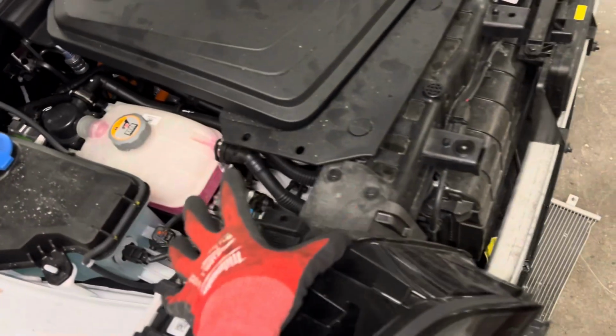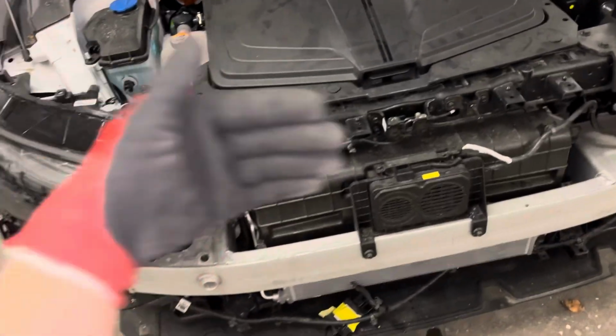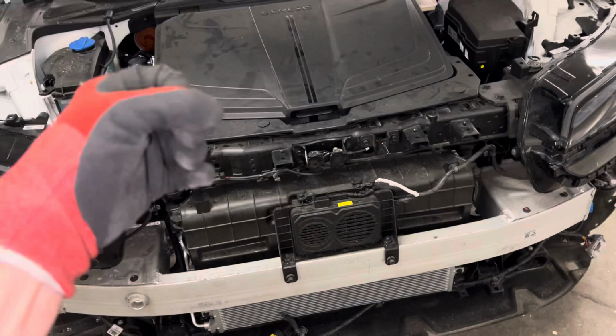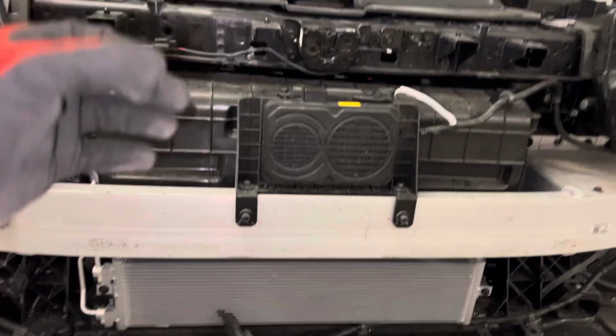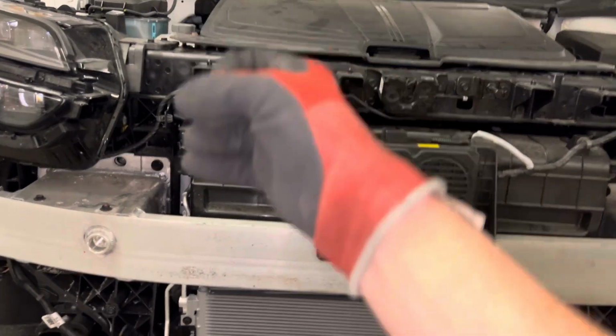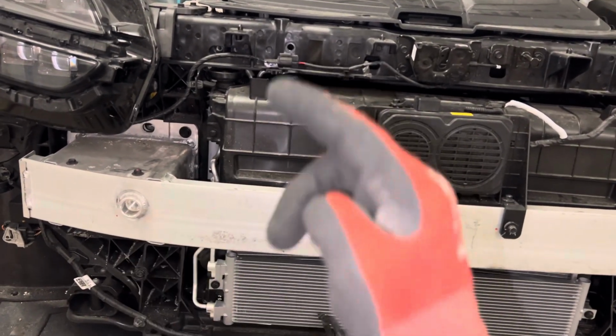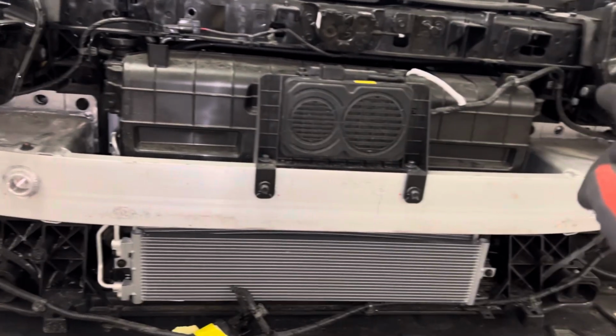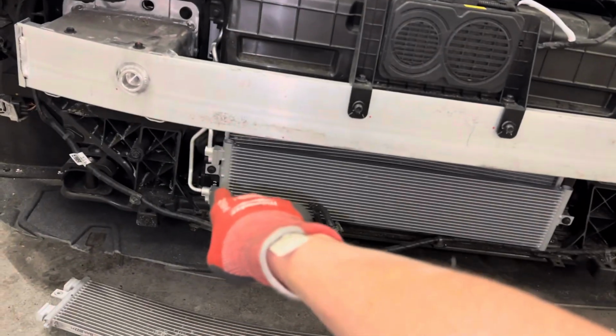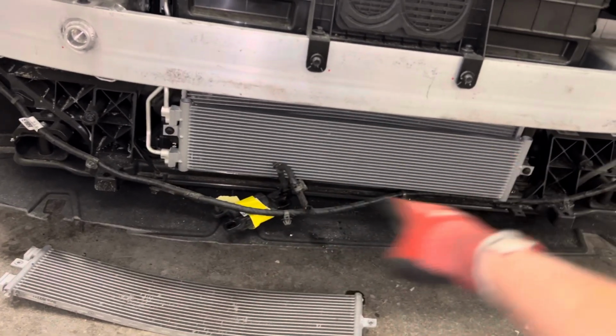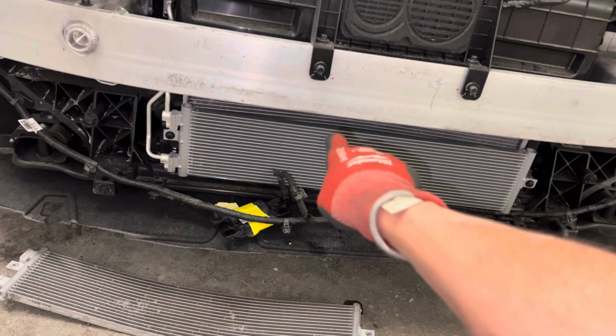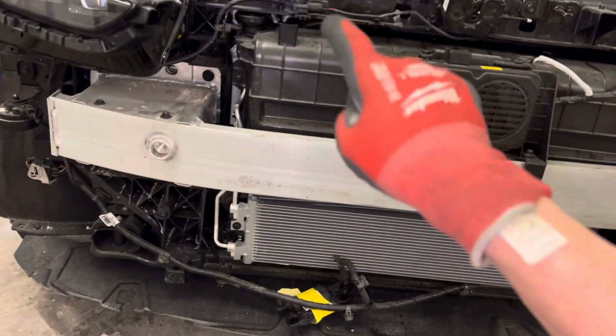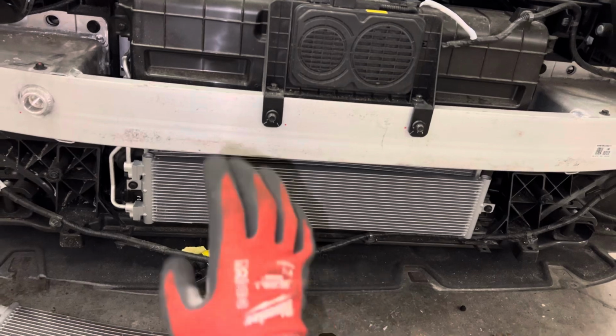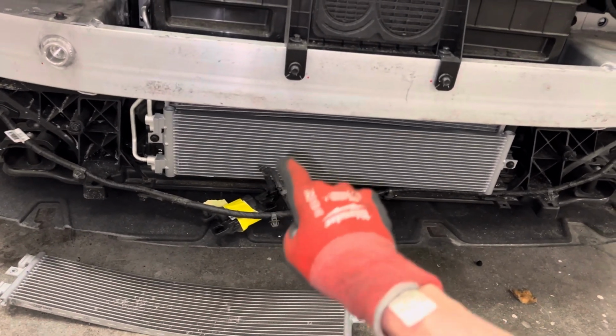That is taking the place of your condenser, doing the condensing part of a parallel flow condenser that would normally have the receiver dryer on the side, the round tube, because it separates the liquid from the refrigerant. But this also has a large accumulator on it too. So after it does its condensing, it comes back and sends the liquid through the subcooler filled with liquid, and performs the subcooling there, then feeds the two expansion valves. That's how this one's working. So that is just a subcooler, it's not the condenser. The condenser is in the glycol loop.